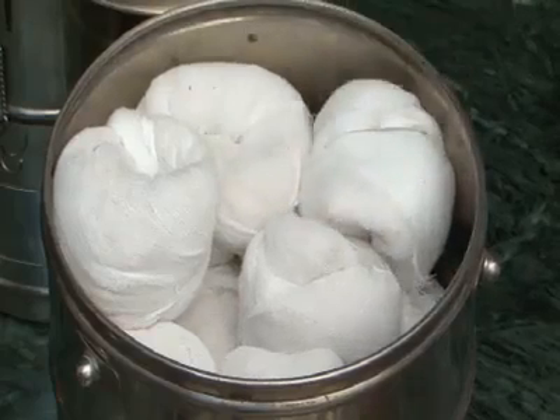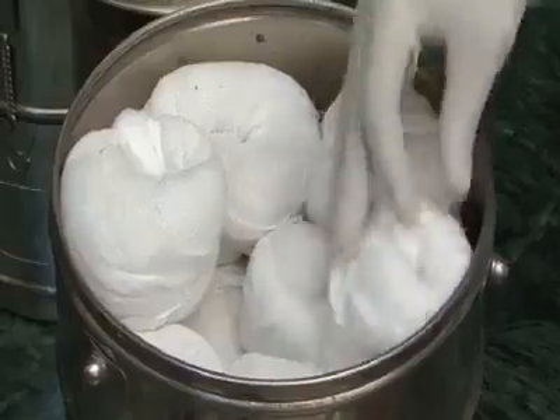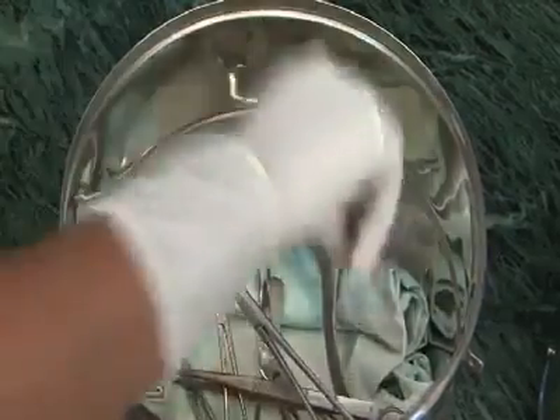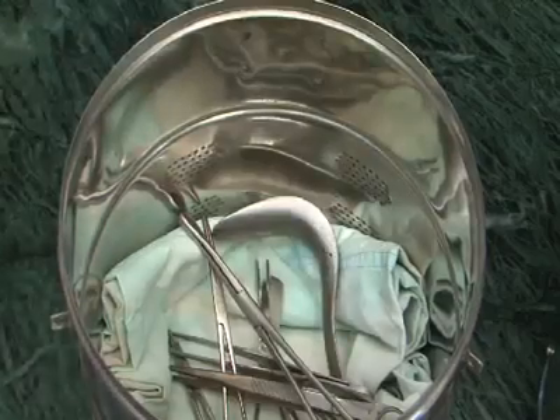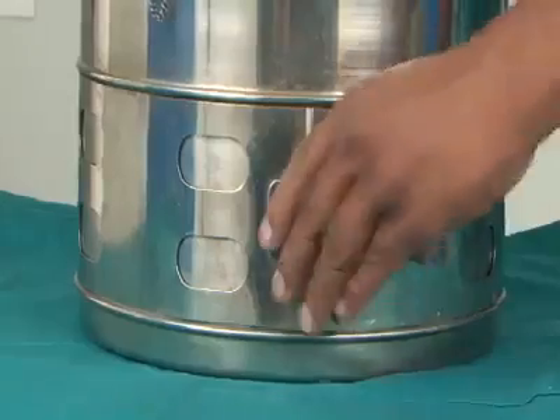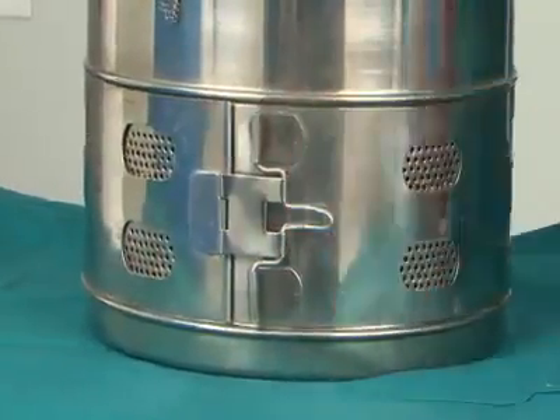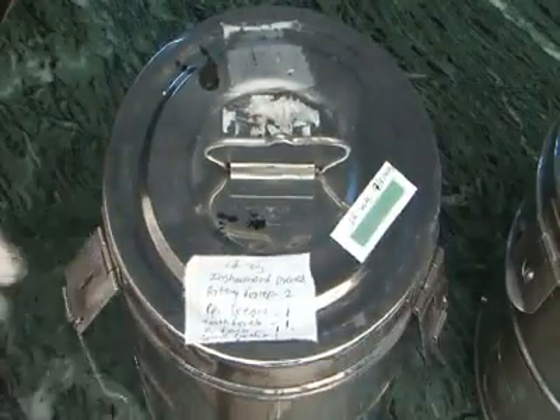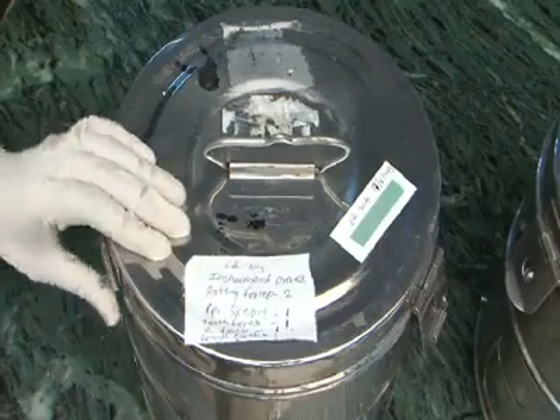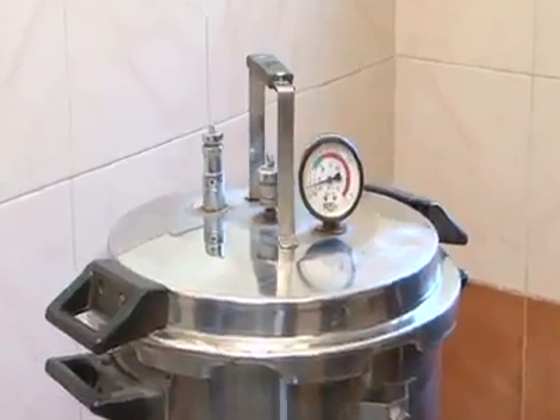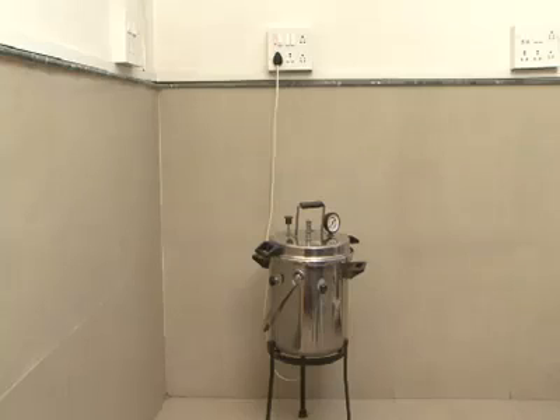For the dressings, pads, cotton swabs, and other loose instruments, etc., are to be kept in a labeled surgical drum having holes in the side, and close the lid. Put indicator strip over the drum. Place the items in autoclave loosely. Then close the lid and put the autoclave on the stove or use the electric autoclave. This allows adequate permeation of steam inside the autoclave.